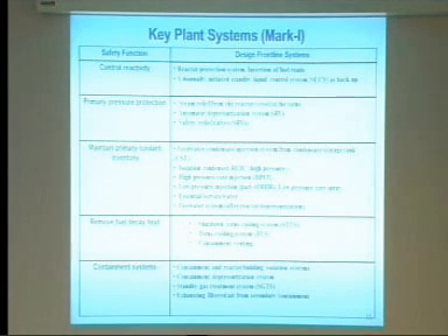There is a way to inject essential service water — which is not a pure water system — into the vessel if needed, but that also requires electric power, which they did not have. However, they were able to connect the fire water system to the essential service water system, which was then connected into the primary system. It's this fire water system that is supplying seawater directly from the ocean through pumps into the vessel to maintain some water level.